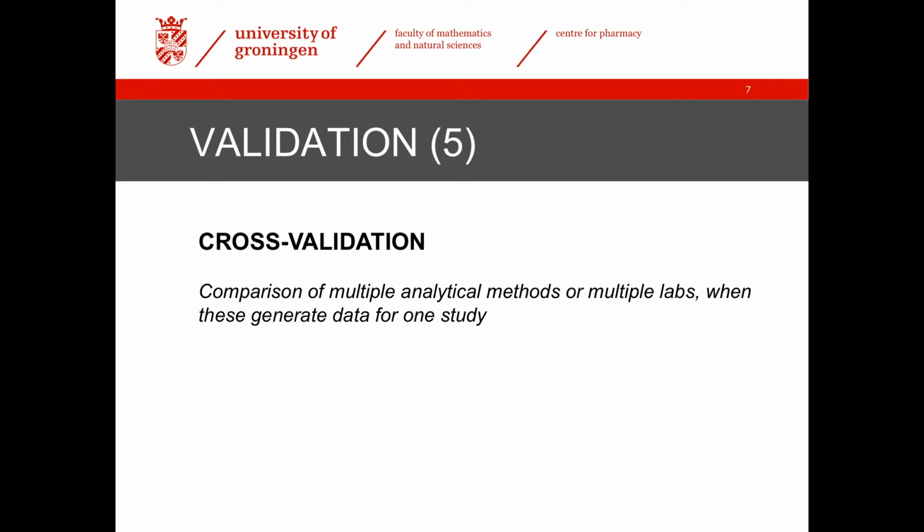It's a more limited investigation of only the aspects that are affected by the changes in the method. Cross-validation is something else. It is a comparison of different methods in one lab, or of one method in different labs, and it simply is the analysis of a single set of samples by the different methods or different labs.